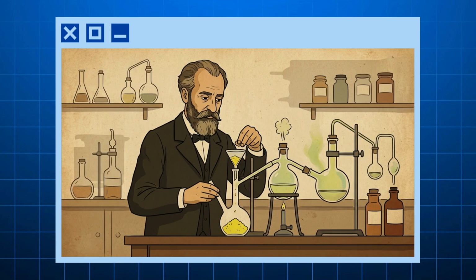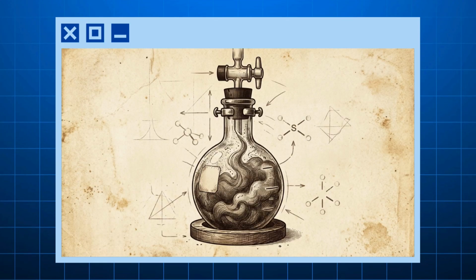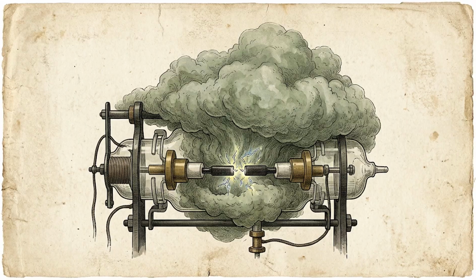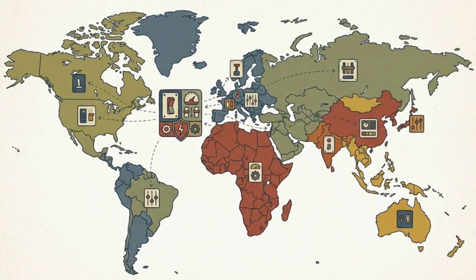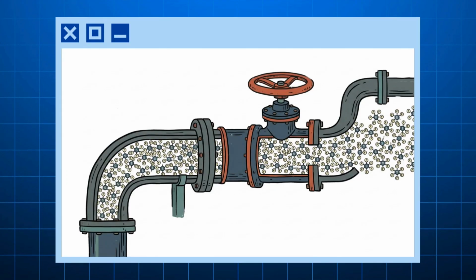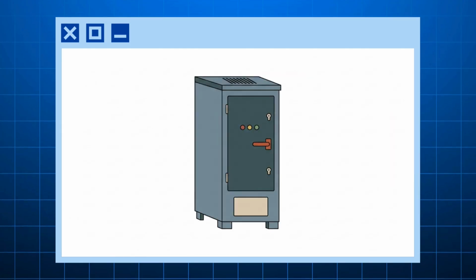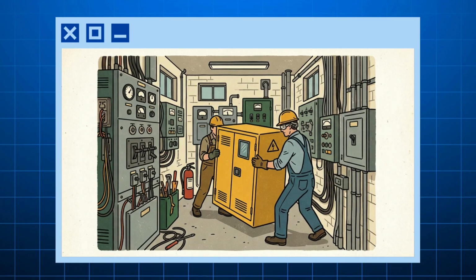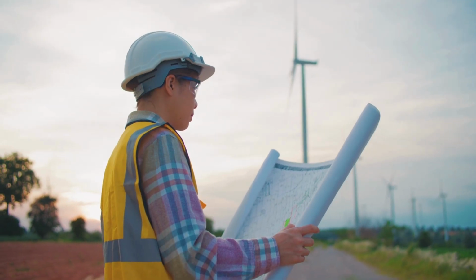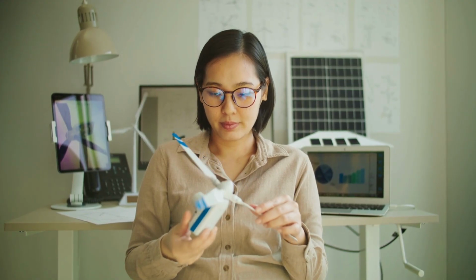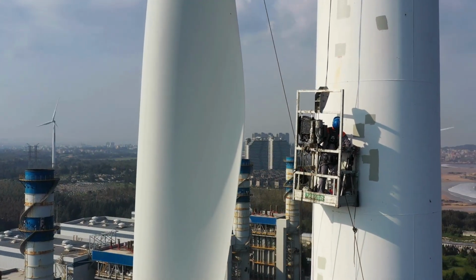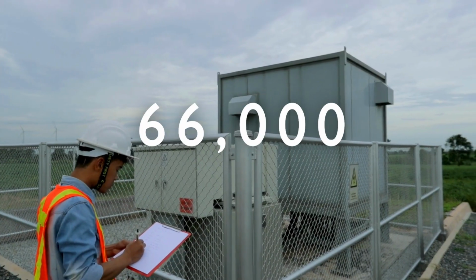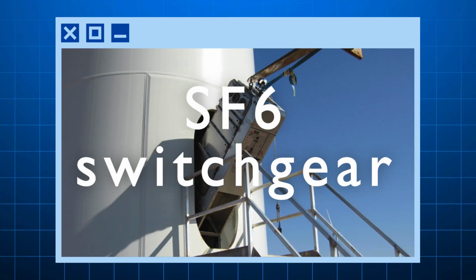In 1900, a French chemist named Henri Moissan combined sulfur and fluorine to create SF6, finding that its heavy, dense molecules acted like an instant smothering blanket over electrical arcs. By the 1950s, SF6 switchgear became the global safety standard. Because the gas was so efficient, safety cabinets could be built small enough to fit inside cramped indoor substations. Decades later, when the wind boom began, developers faced a major spatial constraint. A wind turbine tower is a narrow steel cylinder, and packing 66,000 volts of safety gear inside a 10-foot base left them with effectively one option: SF6 switchgear.